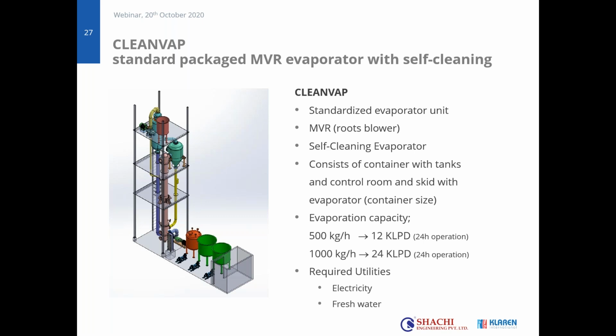What we will effectively do is make a combination between this hot air heating and an electrical heater in the condensate tank. We heat up the condensate until the condensate tank is at 90 degrees. Then we circulate this condensate over the preheater, and at the same time we circulate the liquid that is inside the MVR unit over the same preheater, where normally the feed would run. This system liquid will run, and by this we slowly heat up the unit, or keep it up to temperature, and at the end we combine it with the blower to run on hot air. So those are in fact the three ways for the startup.